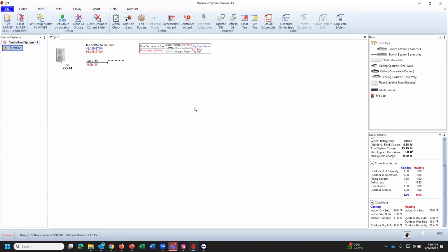So here we wind up with a couple of options. I'm going to go kind of big on the system since we've got a 4-ton outdoor unit. My first joint is we're going to do 2 branch boxes, and we're going to throw in a joint here about 10 feet away from the system. We're going to do that fairly straight and not wind up with any bends.